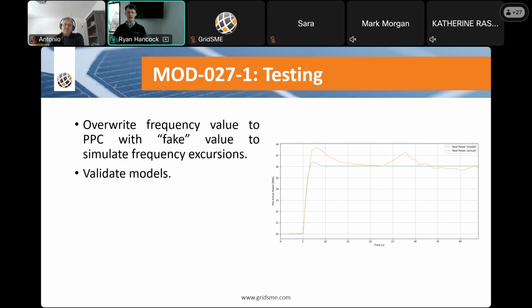And then ideally, we take that data, we adjust the models as they've been submitted thus far, and we start tuning our parameters to make it so that as the plant does this, our model also does a similar thing. So that's kind of for especially mod 26, mod 27, that's how we keep those in line: we take the real world data and we line it up the best we can with the data that feed into our dynamic models.